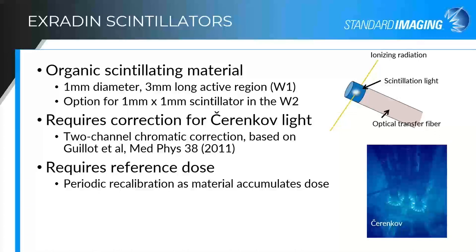Scintillators are not considered absolute dosimeters. They're not something you can send to a calibration lab, get a calibration factor traceable to national standards, and use for a few years. They do require a comparison with a calibrated dosimeter in order to give a reference dose, and periodic recalibration at your machine as it accumulates dose.